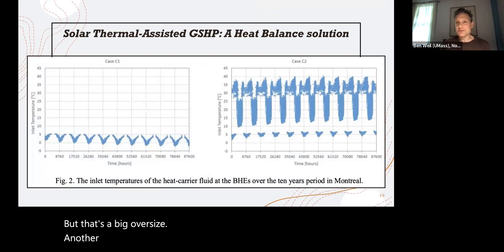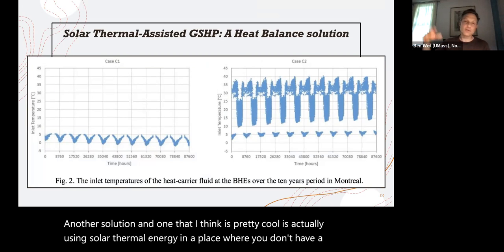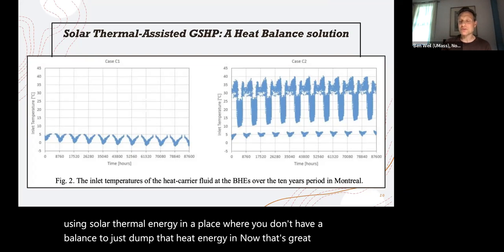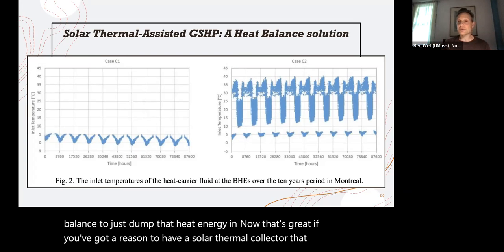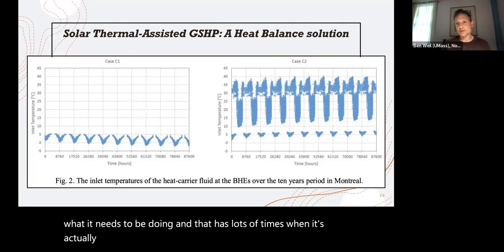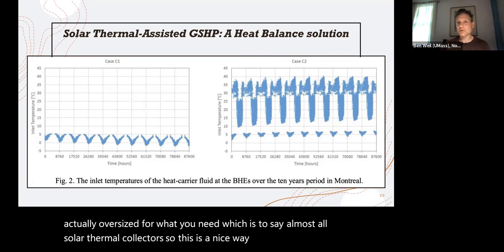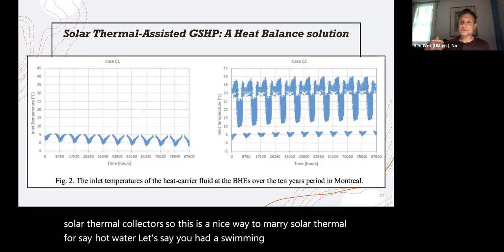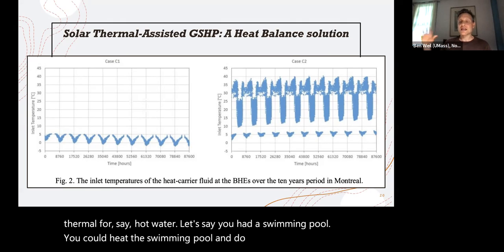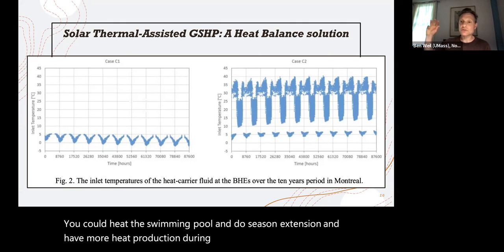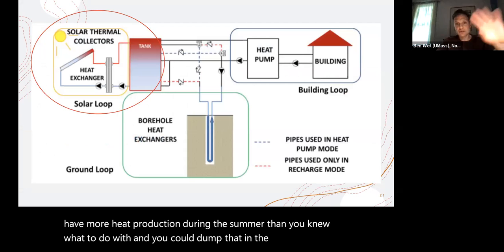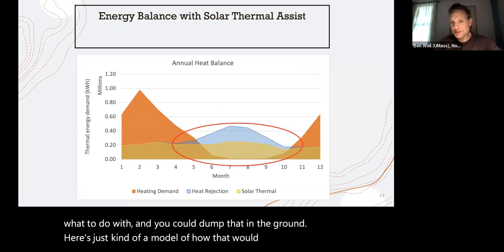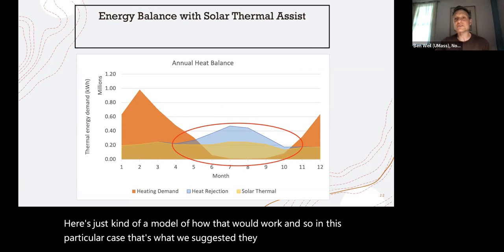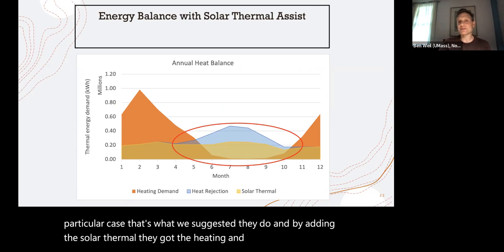Another solution, and one that I think is pretty cool, is using solar thermal energy in a place where you don't have a balance, to just dump that heat energy in. Now, that's great if you've got a reason to have a solar thermal collector that is doing what it needs to be doing, and that has lots of times when it's oversized for what you need, which is to say almost all solar thermal collectors. So this is a nice way to marry solar thermal for, say, hot water. Let's say you had a swimming pool. You could heat the swimming pool and do season extension and have more heat production during the summer than you knew what to do with, and you could dump that in the ground. Here's just a model of how that would work. In this particular case, that's what we suggested they do, and by adding the solar thermal, they got the heating and cooling into rough balance.